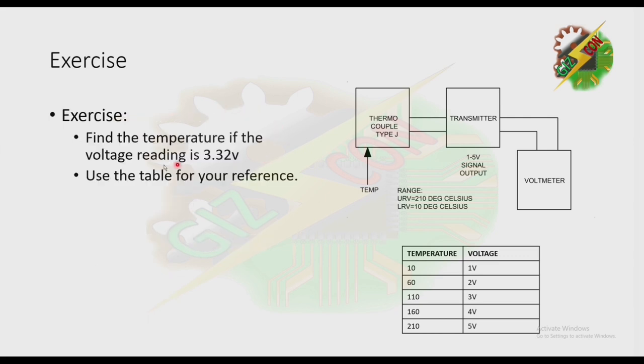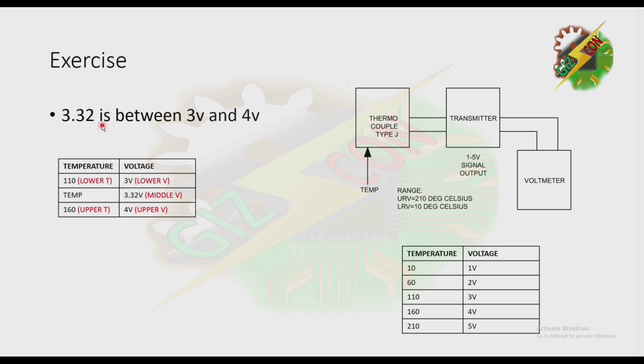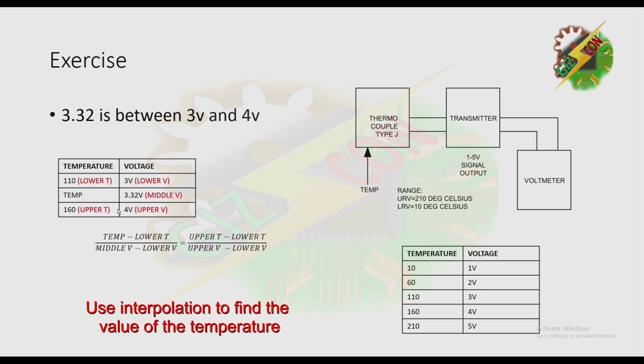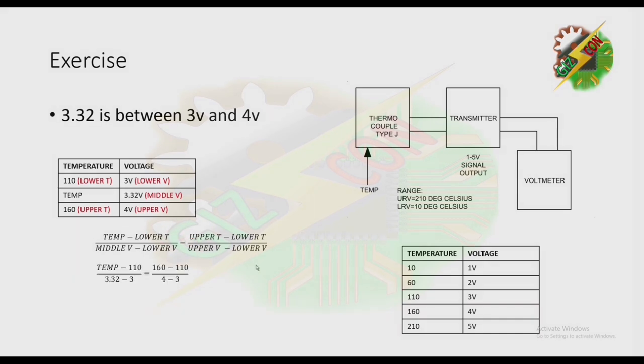Next exercise: find the temperature if the voltage reading is 3.32 volts. Please pause the video and try to solve it yourself. Since 3.32 is between 3 volts and 4 volts, we put 3 volts as the lower and 4 volts as the upper, with 3.32 at the middle. We put the equivalent temperatures from the table. Using interpolation and algebra, the answer is a temperature of 126 degrees Celsius.